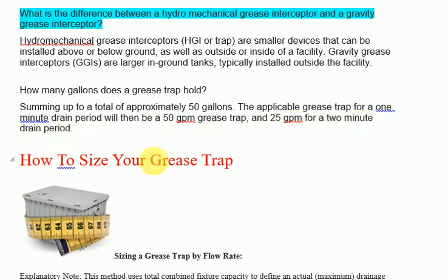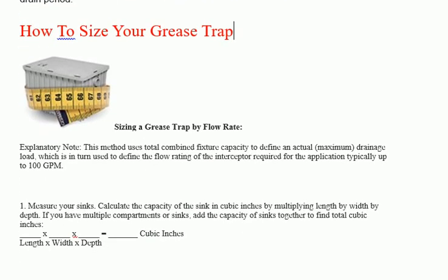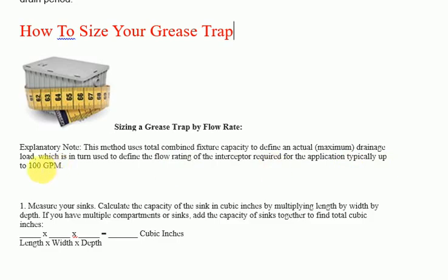How to size your grease trap: This method uses total combined fixture capacity to define an actual maximum drainage load, which is in turn used to define the flow rating of the interceptor required for the application, typically up to 100 GPM.